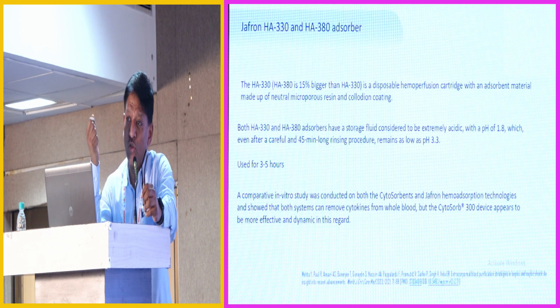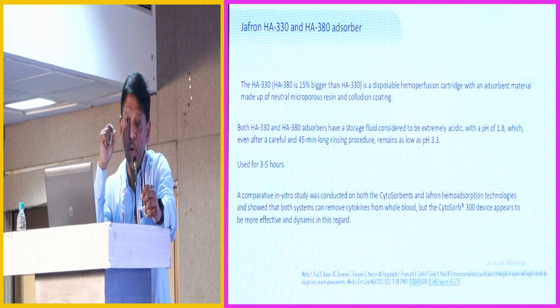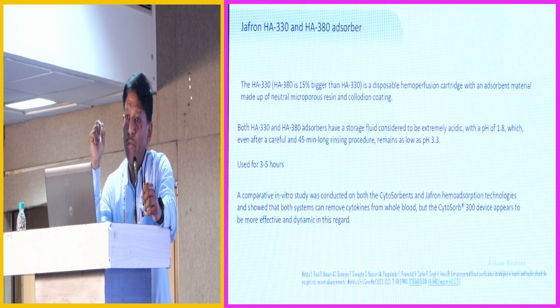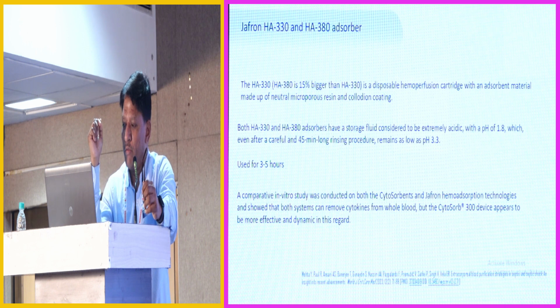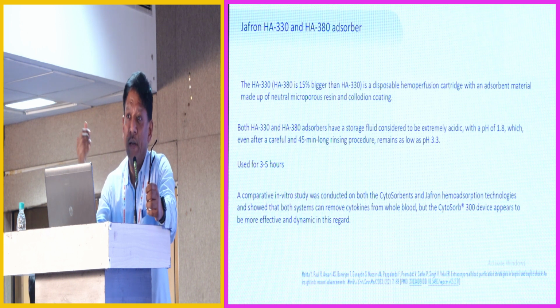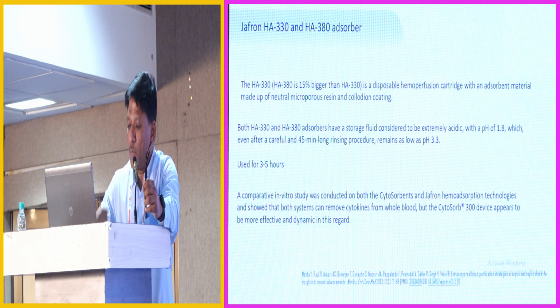So the priming has to be done very religiously by the technician. So 30 to 45 minutes is the priming time, and even after priming, the pH checked was found to be somewhere in the range of 3.3 to 4, which is still acidic. So there are small chances that the patient may develop coagulopathy with this device, but data is not yet out on that. And generally used for 3 to 5 hours.